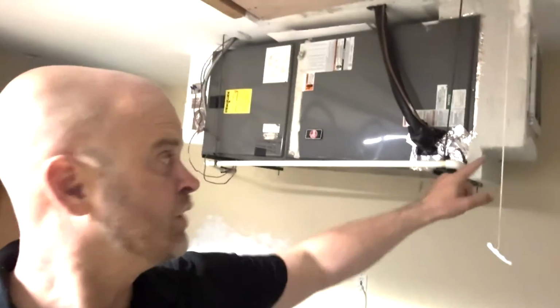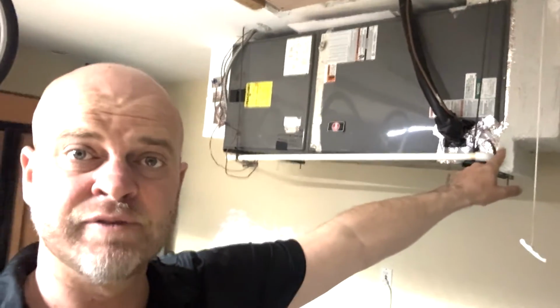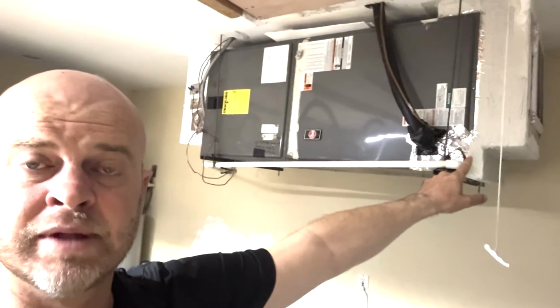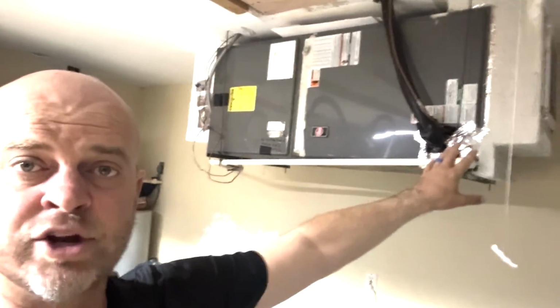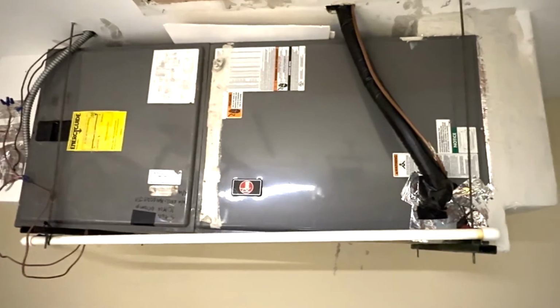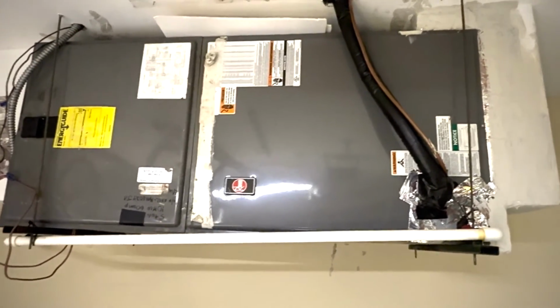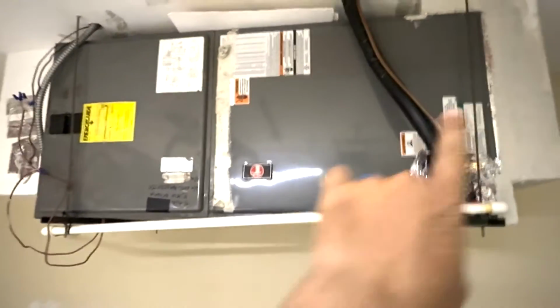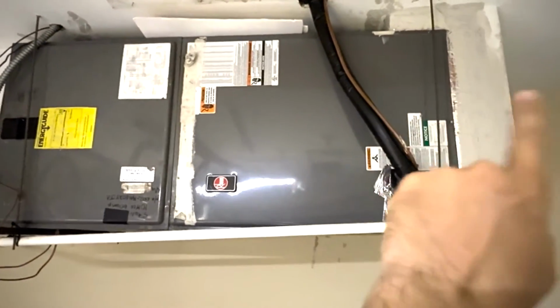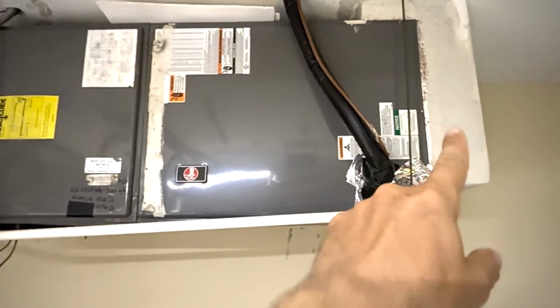You're going to check the temperature difference between the air on one side of your unit's evaporator coil, and then check on the other side, using a temperature probe or a thermometer. The TD, or delta T, TD stands for temperature difference, is the difference across the evaporator coil. So that side is your return side plenum.